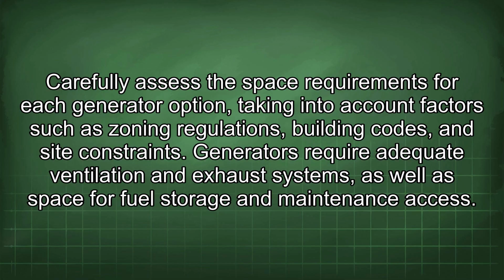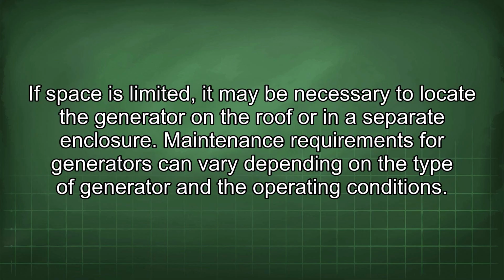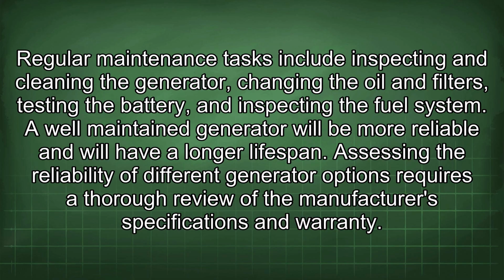Generators require adequate ventilation and exhaust systems, as well as space for fuel storage and maintenance access. If space is limited, it may be necessary to locate the generator on the roof or in a separate enclosure. Maintenance requirements for generators can vary depending on the type of generator and the operating conditions. Regular maintenance tasks include inspecting and cleaning the generator, changing the oil and filters, testing the battery, and inspecting the fuel system. A well-maintained generator will be more reliable and will have a longer lifespan.